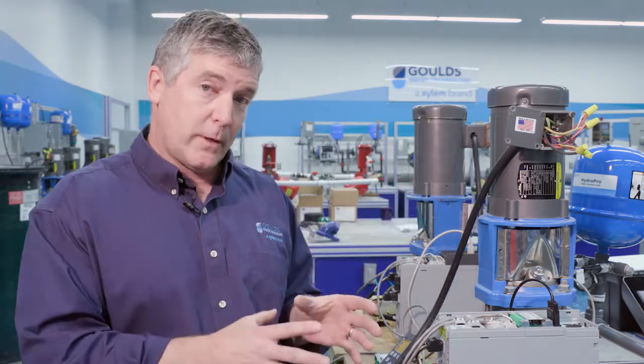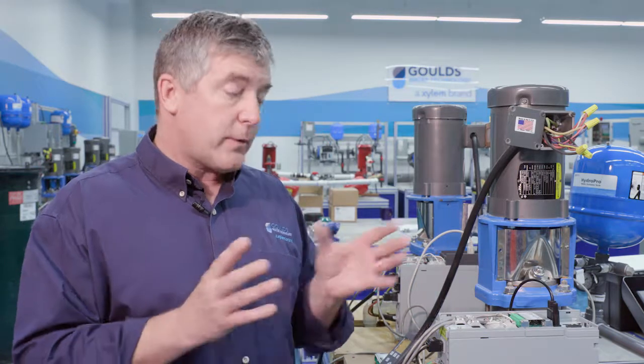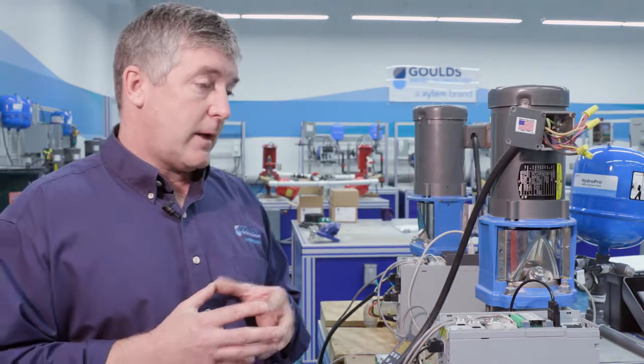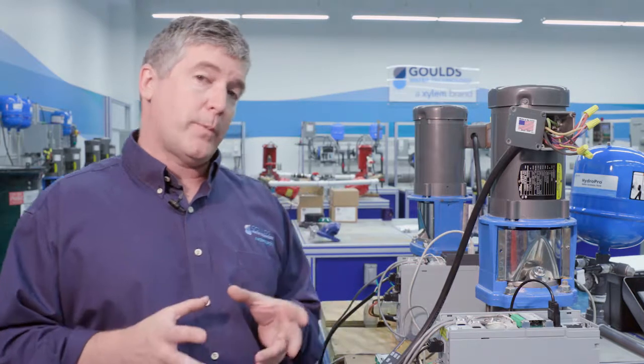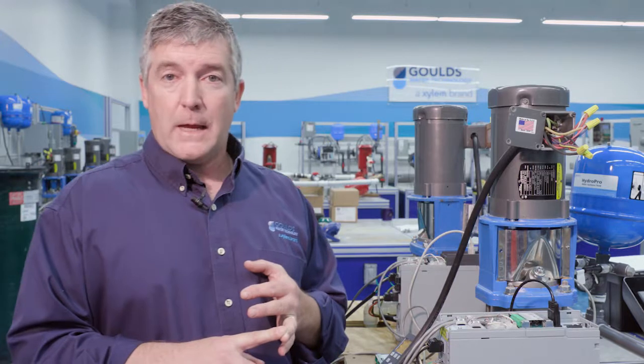The other thing is the multi-pump options that we have. Basic gives you synchronous, and the one other option that we looked at was multi-master, multi-control. So there are other options. So you have additional multi-pump options with the advanced platform. And last but not least is some additional pump protection. So you get high system fault and low system fault, high pressure and low pressure faults, and also a pipe fill function.